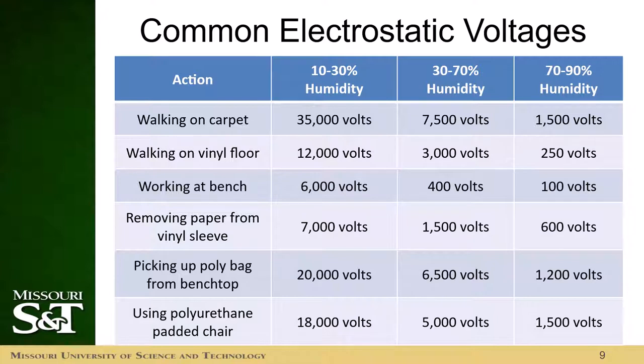Here is a table showing some common electrostatic voltages. You'll see that these are separated by humidity — the lower the humidity, the higher the voltages. It's important that we try to keep the humidity in the lab as high as we can. To do this, we'll have a humidifier in there, especially in the winter months. All the actions shown in the table can cause electrostatic voltages to build up, and these are all things you might be doing in the lab.